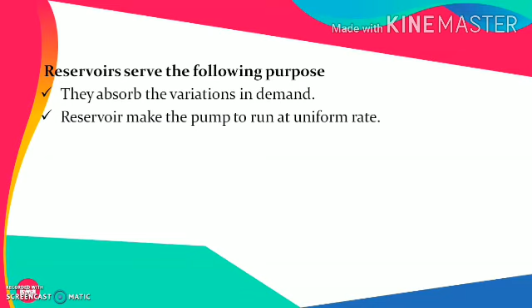So they store the excess amount of water that has been treated in case of low demand or no demand, while they make the water available when there is a high demand, particularly in the morning and in the evening in case of residential needs. They make the pump run at a uniform rate because they are allowing water to pump at the rate at which it has been treated.